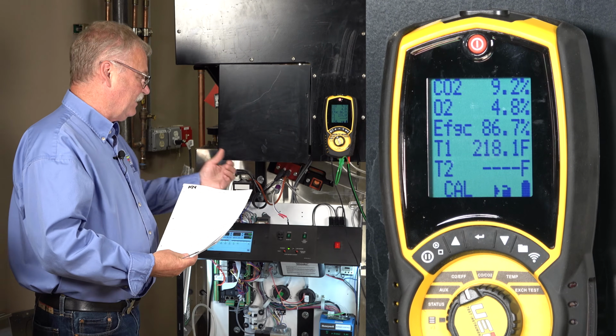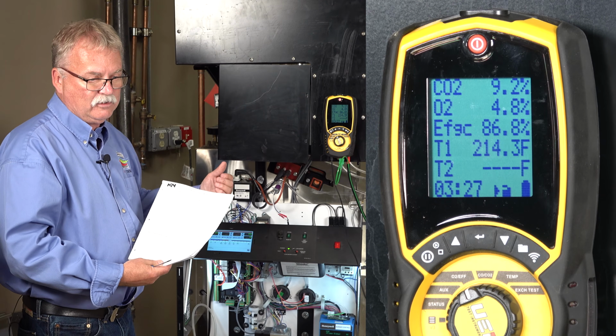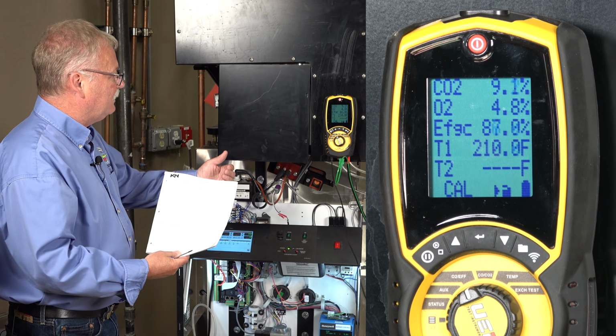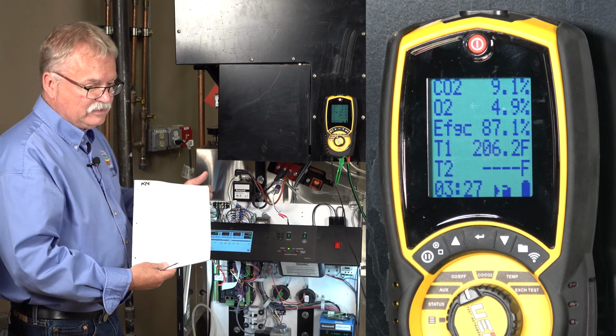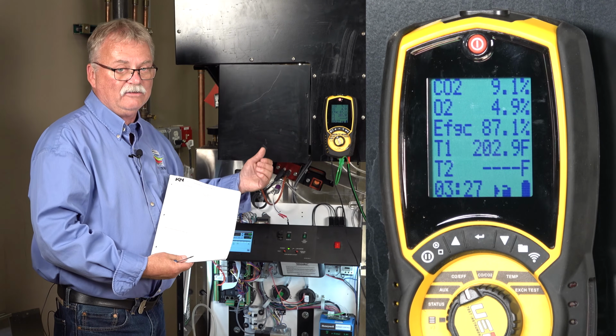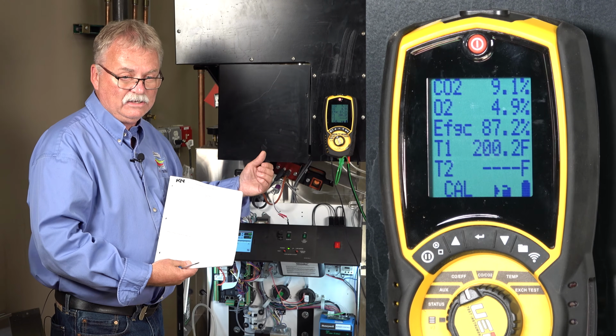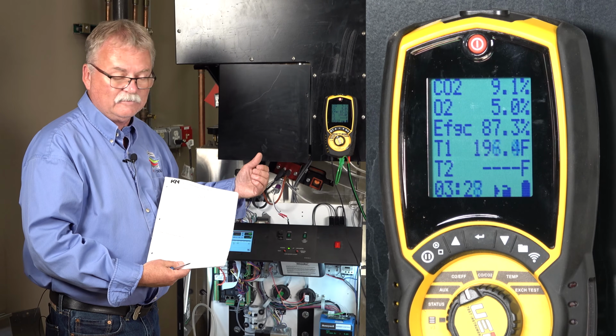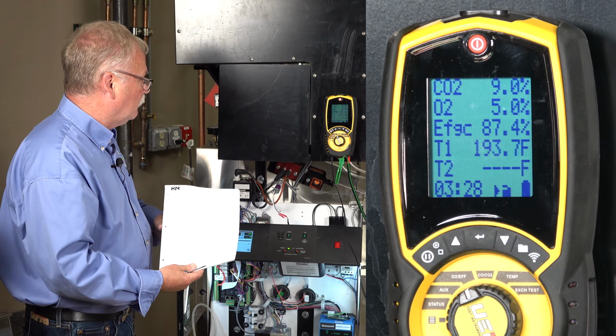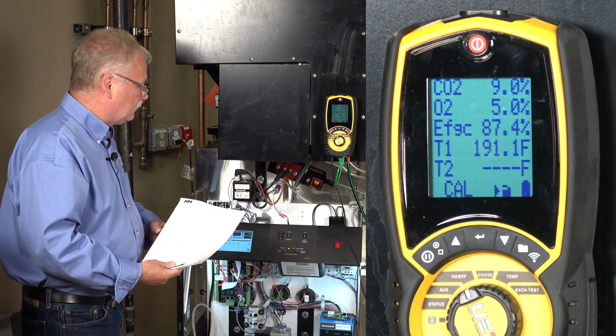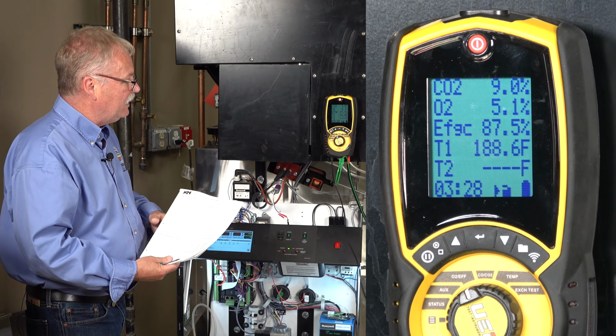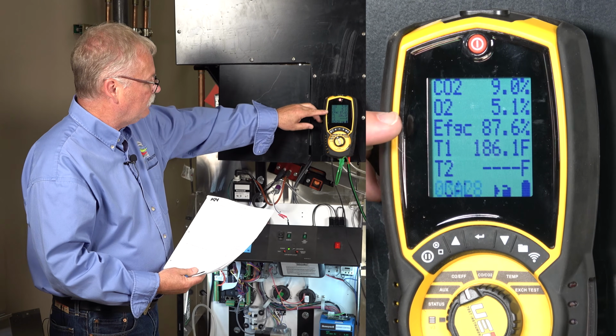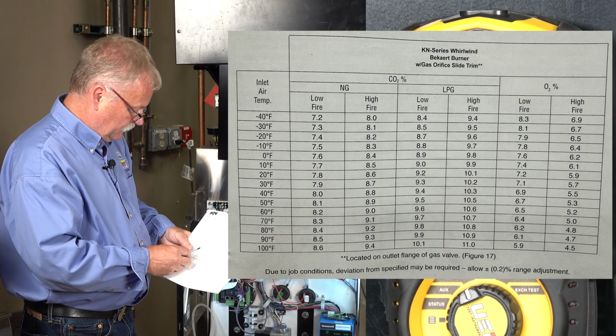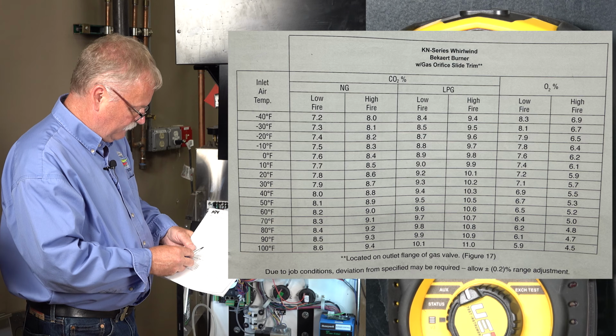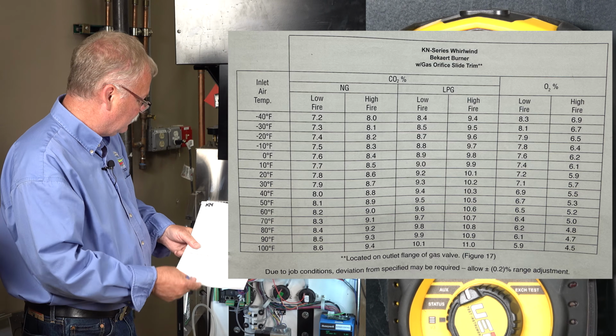This boiler, I can go either way on it as far as high fire or low fire first. They're not that far out of range. Most of the time when you get a new boiler, you're not going to find it dramatically out of range unless somebody's just played with it. Okay? So basically now we're going to see low fire is coming down. Our efficiency should start going up. And we're going to try to get our CO2 at about 8.5, 8.4, 8.5 on this thing.